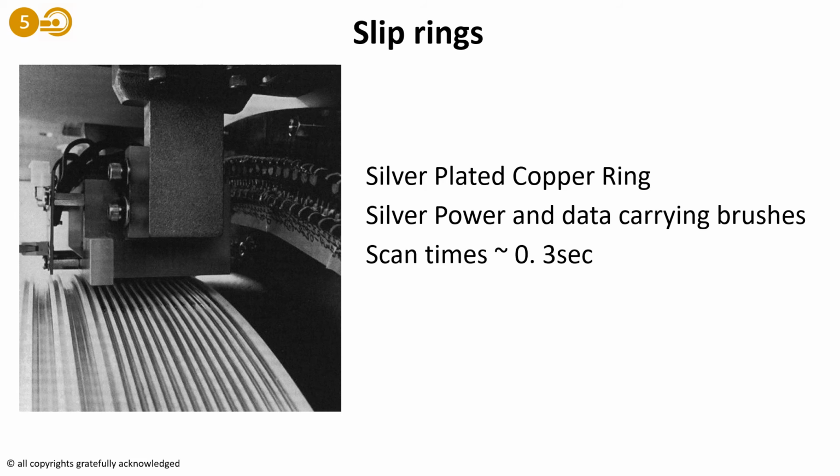One technology that did not exist at all in the early days of CT, but which has become essential to enable the continuous rotation of the X-ray tube and hence spiral CT, is slip rings. While there were fewer technical barriers to the development of slip rings than in other areas of CT, and there have been fewer changes in the technology over the years, it is still a key and essential technology for the modern CT scanner.